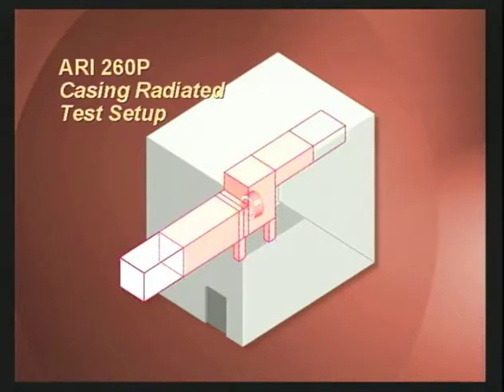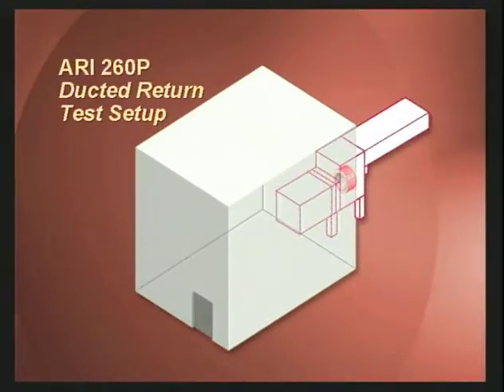In the third setup, we're looking specifically here only for the casing radiated noise. Again, the product is mounted within the reverberant room. However, both the discharge and the inlet are ducted outside the room so that we get only the casing radiated noise. And finally, if we have a specific case where we need to know the ducted inlet, we then again, as with the discharge case, duct the inlet into the reverberant room to measure that component. For each of these test setups, we measure each of the components across the full operating map of the product as defined by the manufacturer. In addition, if the product has multiple taps, such as a case of a discharge with a discharge plenum and two discharge ducts, each one of those discharges has to be tested independently.